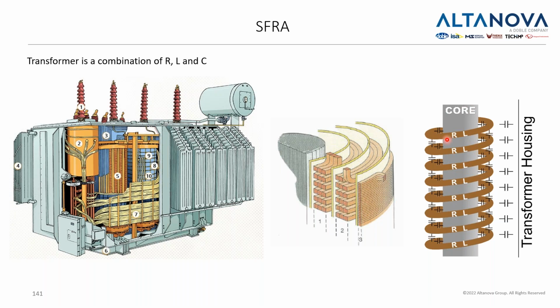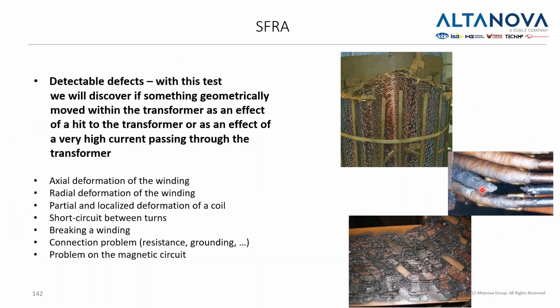You have here the resistance of the coil, you have inductance, and you have the parasitic capacitance, let's call it, between two windings, between the winding and the housing, etc. As you change the frequency from a few hertz to a few megahertz, you will get a type of transfer function, which I will show you later. But before that, I will tell you what the detectable defects are. With this method, the most important thing to mention is that this is the best method to understand if something geometrically moved inside the transformer.